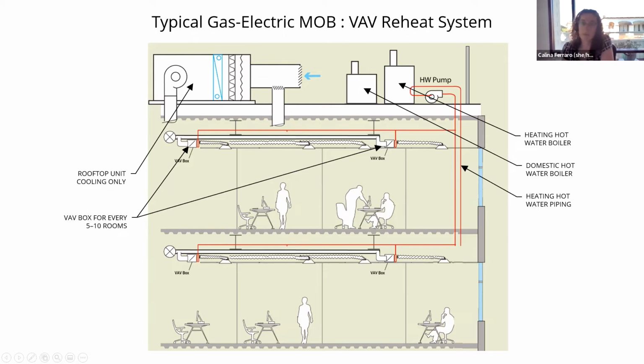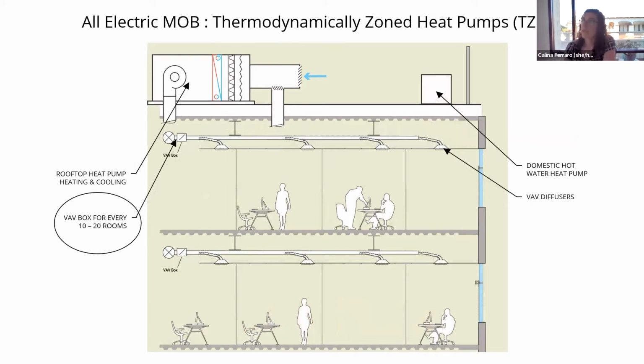So there's a certain amount of complexity associated with that, just because we've got multiple systems using multiple energy sources, having to do both of those functions simultaneously. The advantage that we got with our thermodynamic zoning is that we're not doing both cooling and heating at the same time in each zone. So we can do either the cooling or the heating all up at that unit. This unit can do either cooling or heating, but it happens at the roof. So the air is already either warm or cool, depending on what the zone needs, when it leaves the unit, which means that we can distribute that to the zones as they need it, and it eliminates that secondary system for the hydronic piping. That saves energy because we're not cooling and reheating, but it also saves us all of that complexity. So it's a much simpler system.